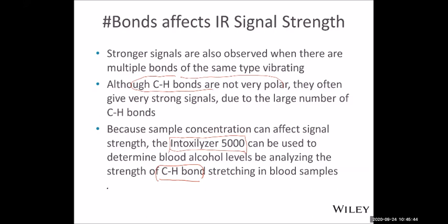Because our exhaled breath has lots of nitrogen gas, oxygen gas, water, and CO2, fairly significant, and the alcohol, the ethanol. Among these molecules, nitrogen and oxygen have no infrared because both are non-polar molecules. Water has infrared, very significant, around 3300, a very wide peak. Carbon dioxide is around 2000, because of the carbon-oxygen double bond. The ethanol has O-H. The O-H will overlap with water, so we cannot use O-H to quantify the alcohol in the breath.